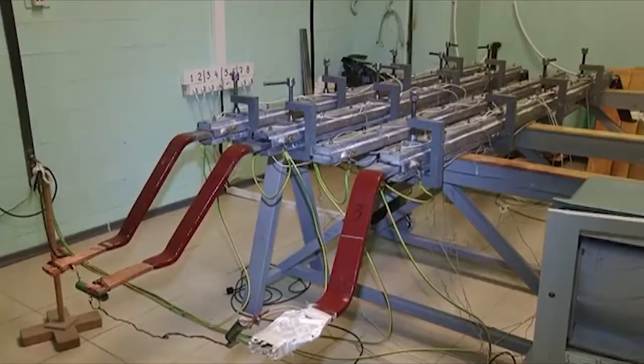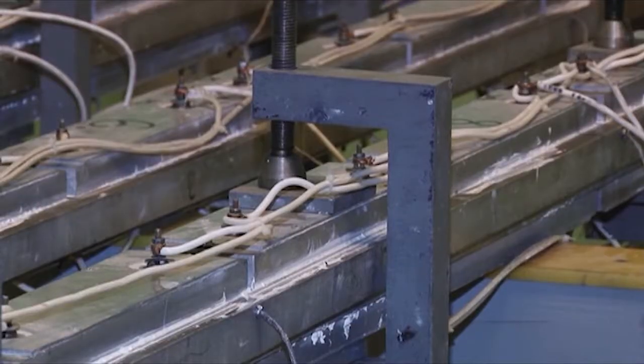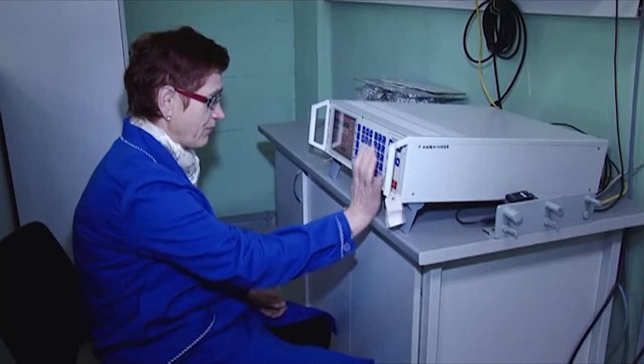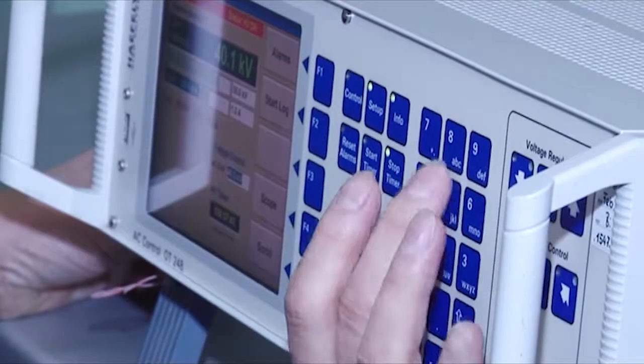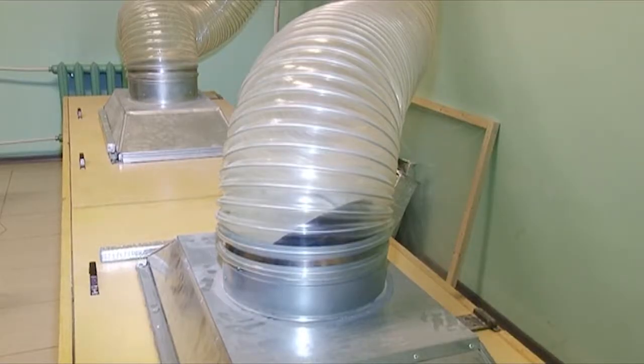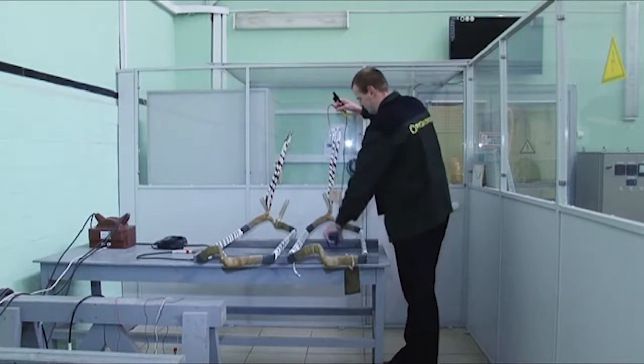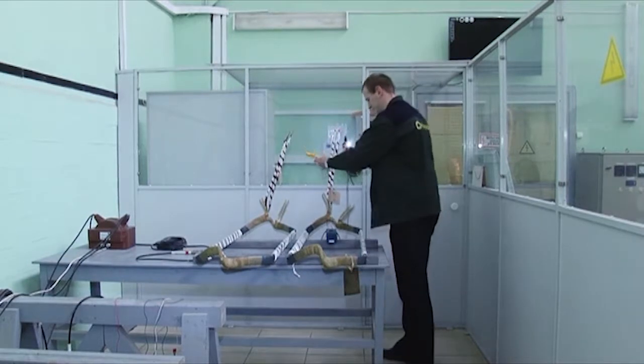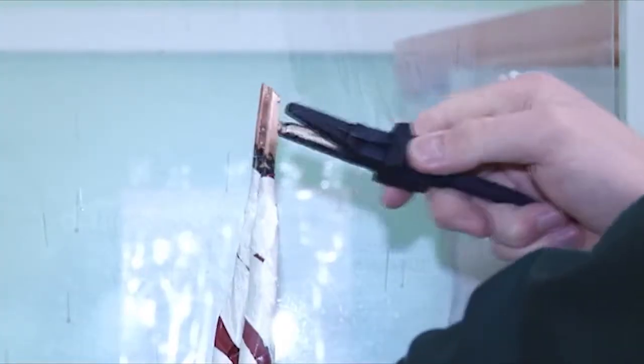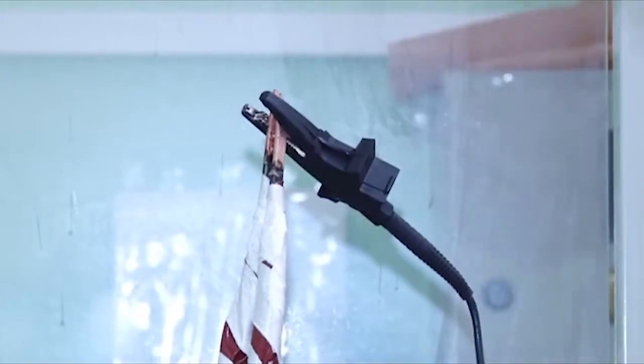The voltage endurance test is performed to determine the insulation service life. Two factors influence the insulation: a temperature of approximately 100 degrees centigrade and increased voltage. The successful outcome of the voltage endurance test guarantees the insulation service life for 25 years. The thermal and mechanical stability of the insulation is determined during thermocycling tests. To measure the insulation resistance, 2.5 kV of DC voltage is applied. The measured insulation resistance value shall not be less than 500 megohms.